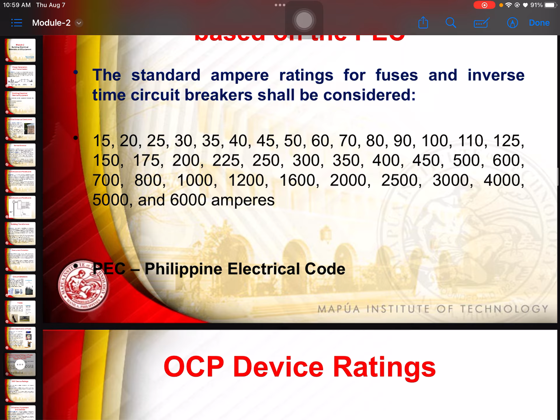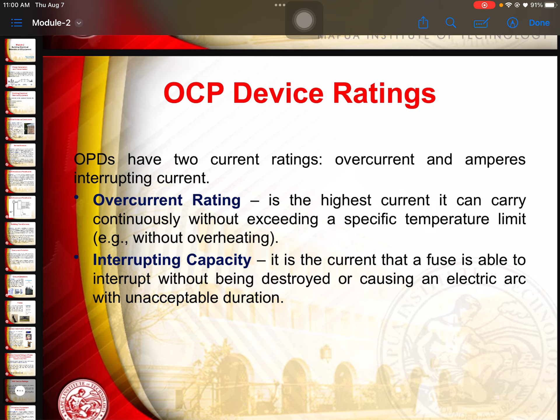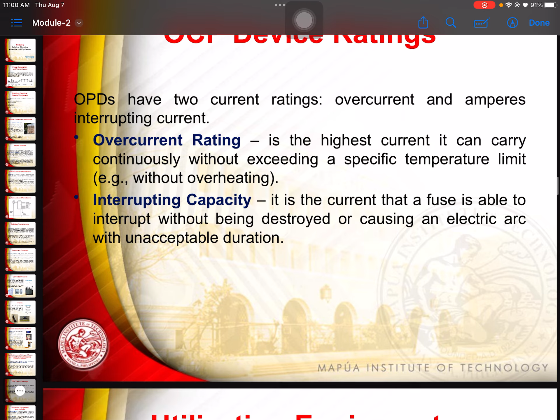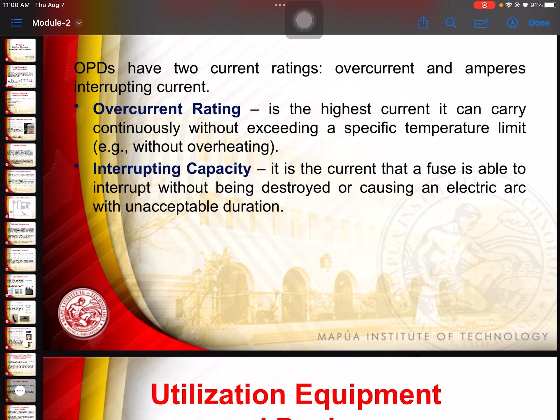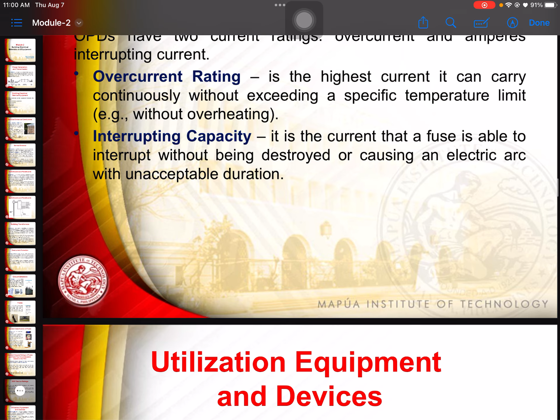OCP device ratings: OPDs have two current ratings—overcurrent rating and ampere interrupting current. The overcurrent rating is the highest current it can carry continuously without exceeding a specific temperature limit, meaning without overheating. The interrupting capacity is the current that the fuse is able to interrupt without being destroyed or causing an electric arc of unacceptable duration.